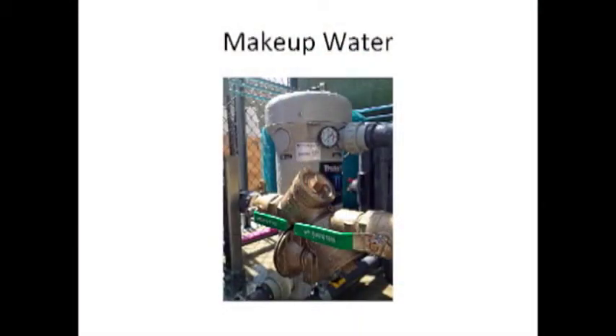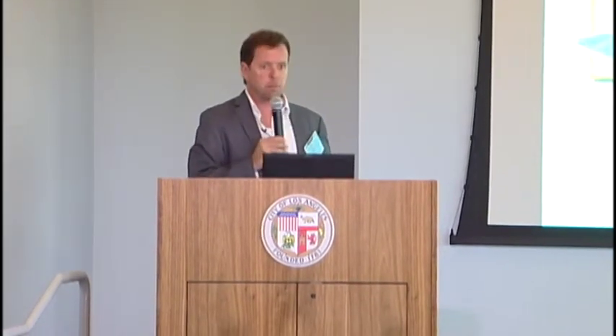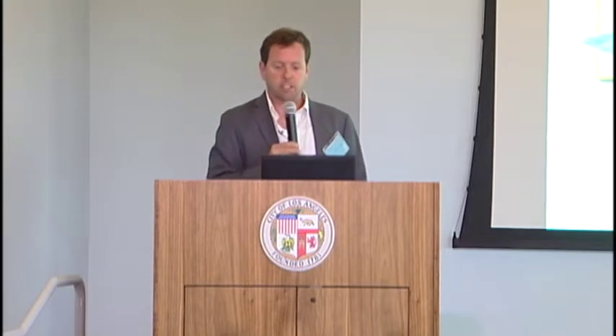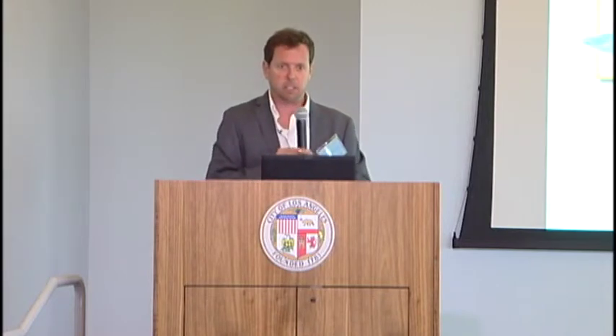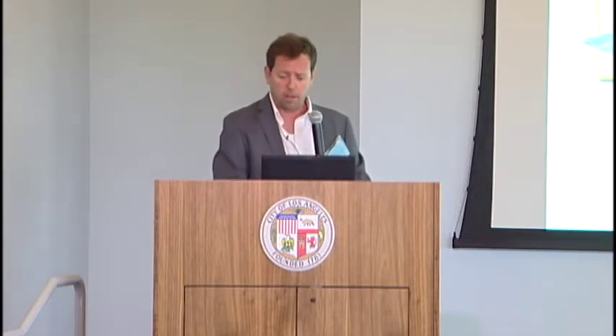Makeup water is a critical element of any stormwater cistern here in Southern California, because for all practical purposes, when you want the water, it doesn't rain. It's something that should be included in any design element; otherwise the reuse system doesn't really serve its full purpose. An air gap is a very simple mechanism by which pressurized city water can be introduced into the tank without running the risk of a cross-connection. If there's any backup, the water overflows out and doesn't make it into the city pipe. That applies to graywater equally so.